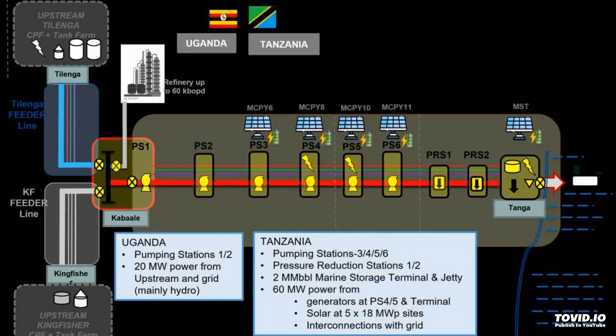Safety staff will be able to detect any pressure change indicative of a leak, sabotage or pilfering within seconds and isolate the relevant section of pipe to keep any environmental damage and commercial loss to a minimum. Both the PAU and EACOP's holding company will have real-time monitoring centers at their respective offices to receive immediate updates via satellite uplink. This means that monitoring is not dependent on local mobile phone or radio networks, guaranteeing greater reliability.